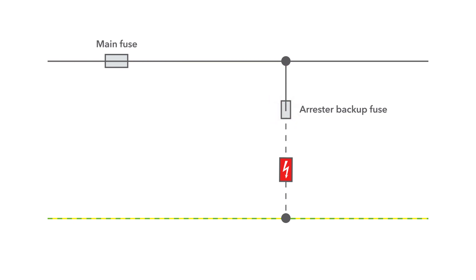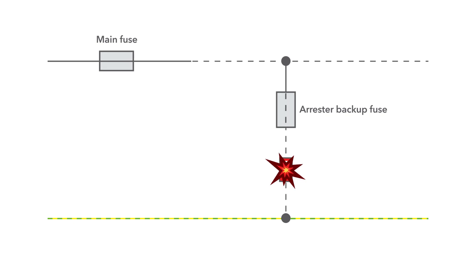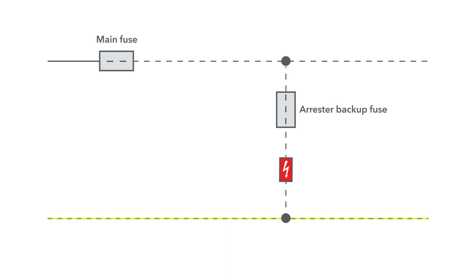Conversely, if the backup fuse is too large, there is a risk that the arrestor will explode or be thermally overloaded in the event of a fault.